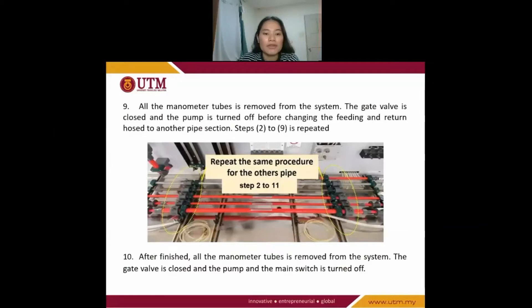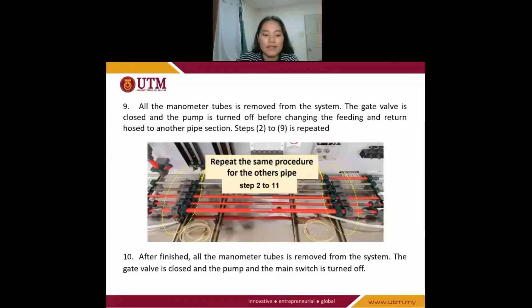Next, if there are no air bubbles, the ventilation valve is closed and the flow rate Q, pressure, and differential pressure readings are recorded. Then all manometer tubes are removed from the system. The gate valve is closed and the pump is turned off before changing the feeding and return hose to another pipe section. Steps 2 to 9 are repeated.